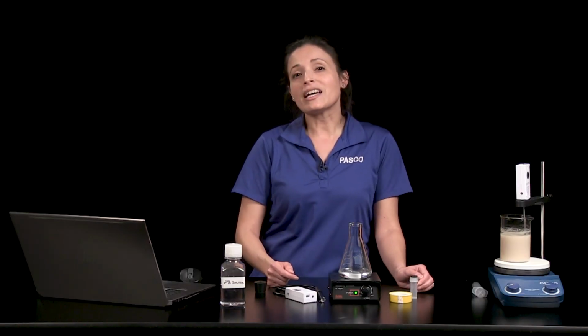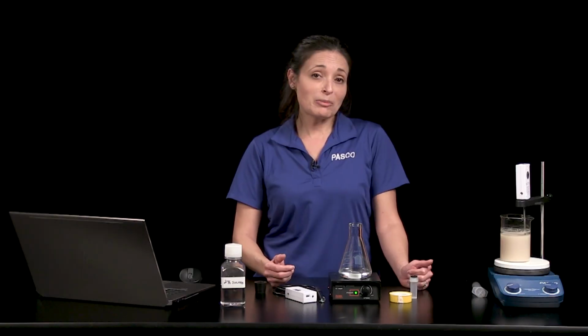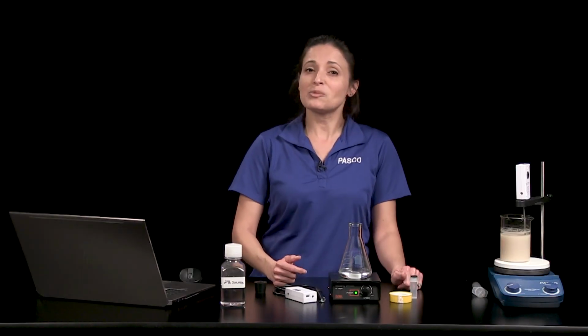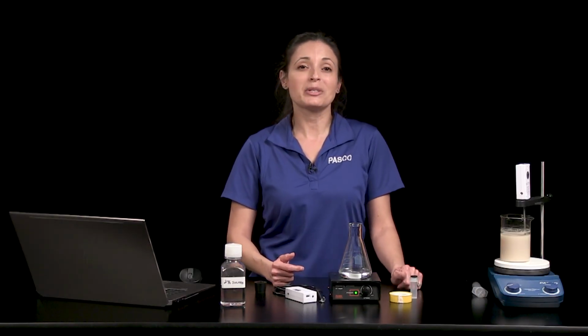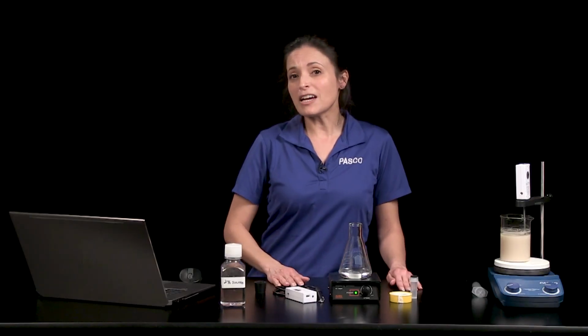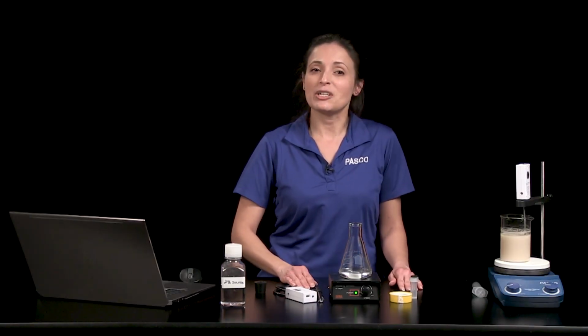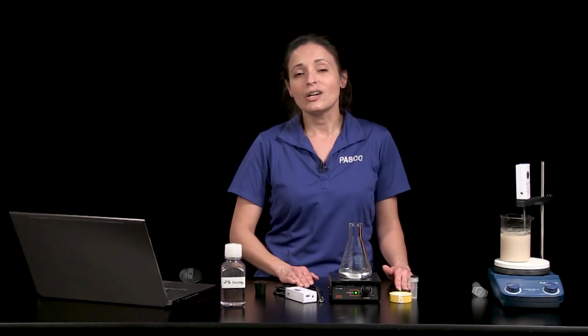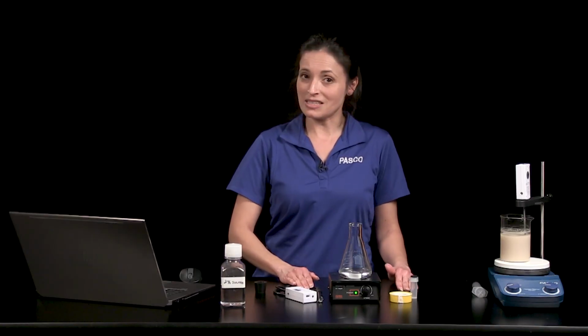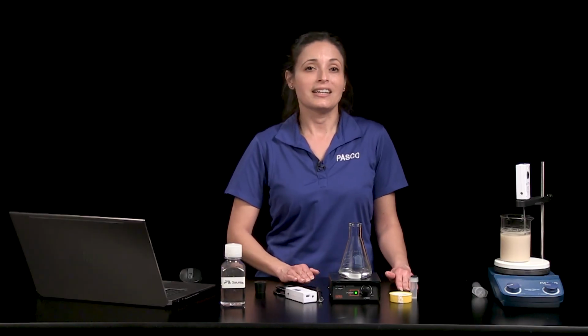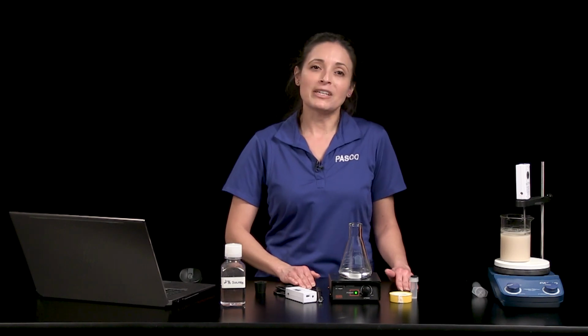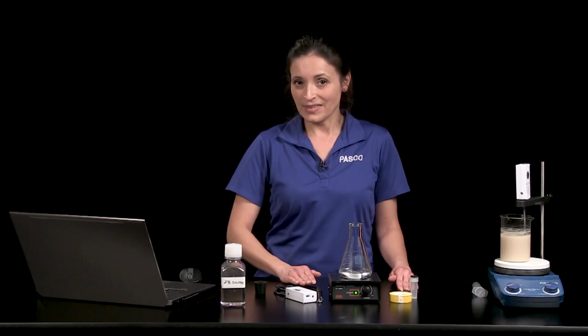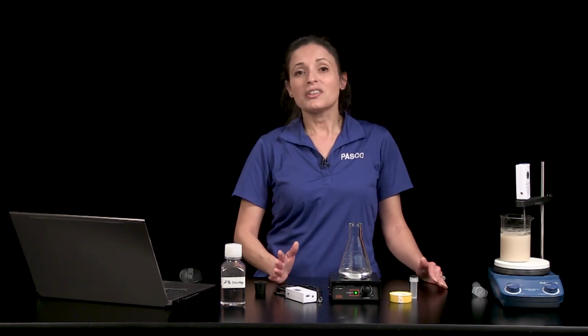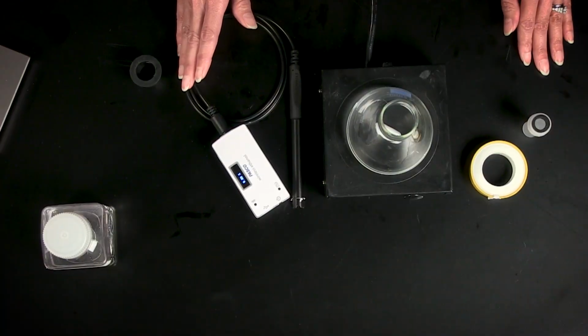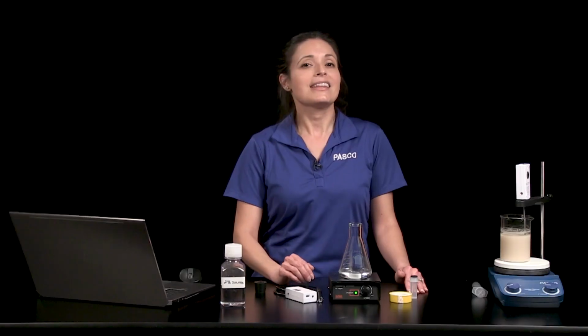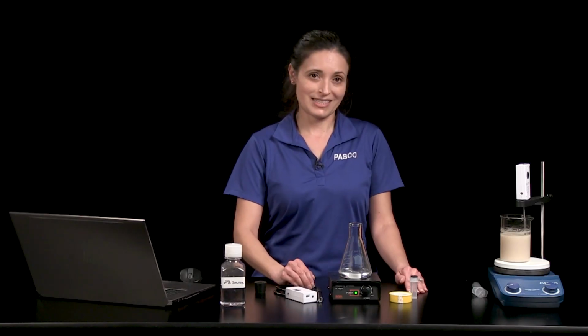The sensor can be calibrated in any container, but we provided this small vessel to speed up wait time for liquid-vapor equilibrium. The sensor is factory calibrated and will only need calibration before a quantitative analysis, or if the sensor is not reading within 0.01% of zero in ethanol-free air after it has warmed up. As with other gas sensors, the wireless ethanol sensor with display needs a few minutes to warm up. Then after warm-up, you can take measurements.